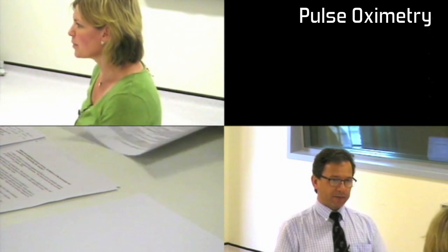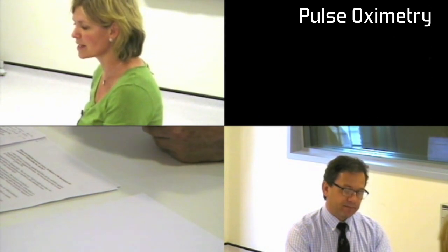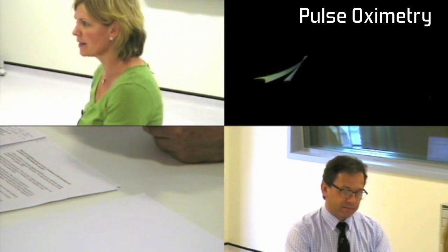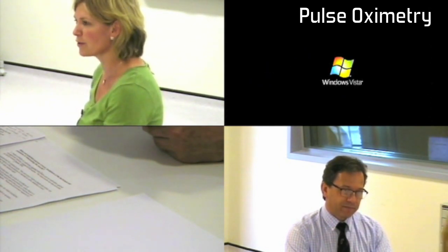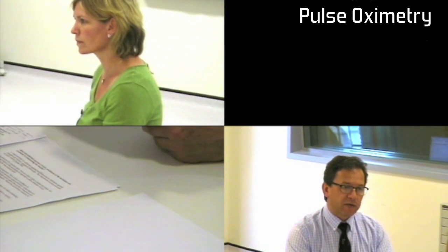Can you tell me how does the pulse oximeter work? The pulse oximeter is a non-invasive device that we use in anesthetics to measure oxygen saturation. It consists of a peripheral finger probe and a processing unit and a display unit. The finger probe contains two light-emitting diodes that send light through the chosen tissue and the photodetector on the other side.